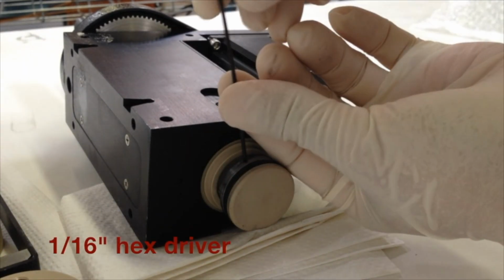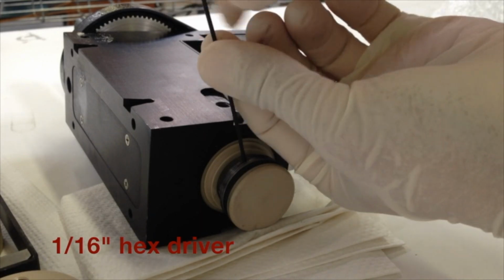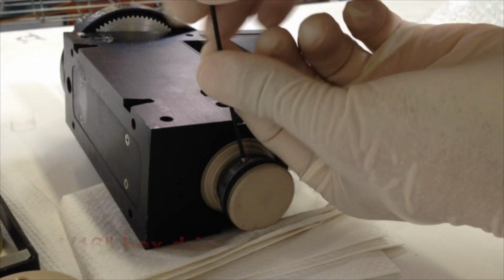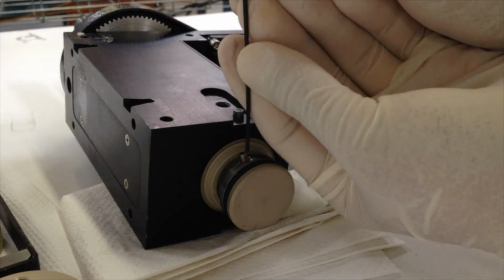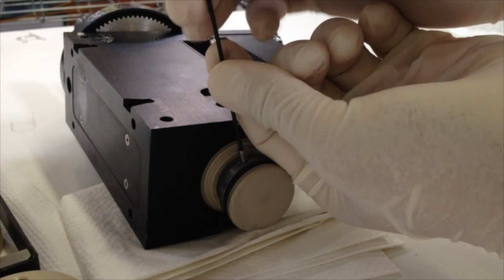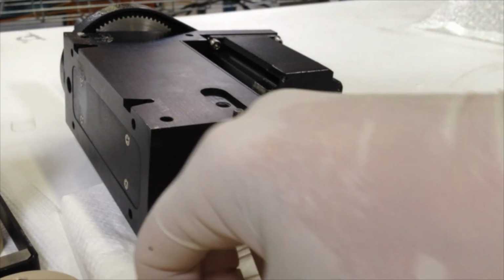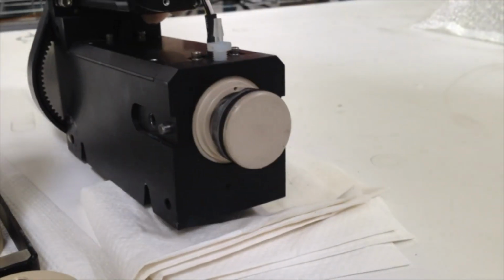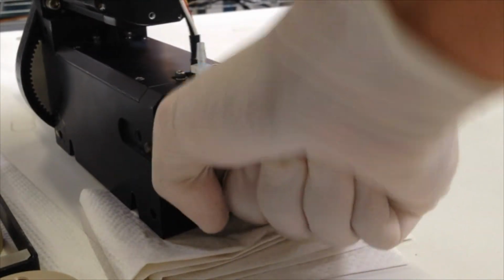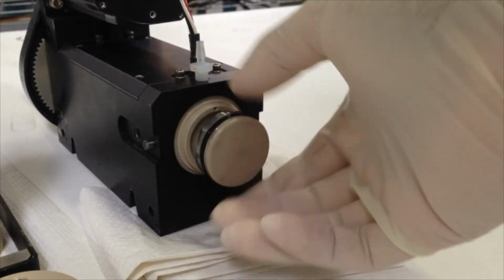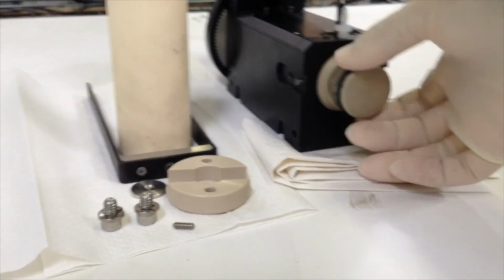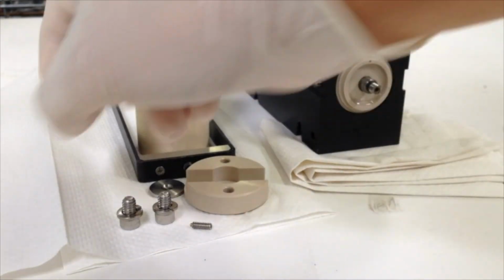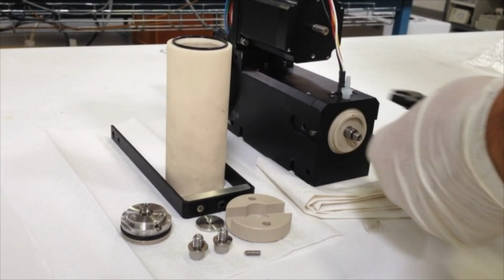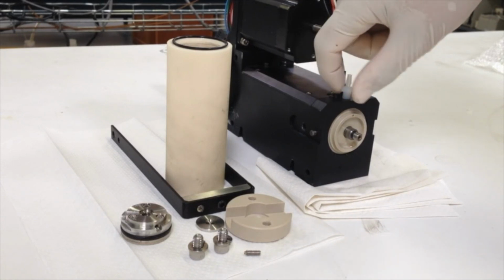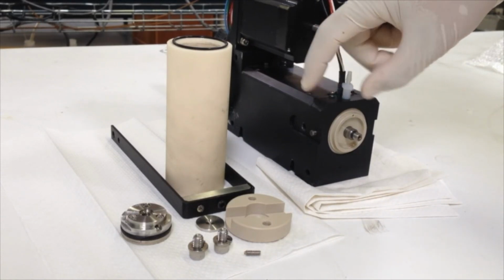Completely remove the brass-tipped set screw with a 1/16 inch hex driver. Do not reuse the brass-tipped set screw. Remove the pump head by twisting in a counterclockwise motion. Completely remove the piston wash connector. This will unlock the piston O-ring guide, and you can now turn the lead screw until you are able to pull off the piston O-ring guide.